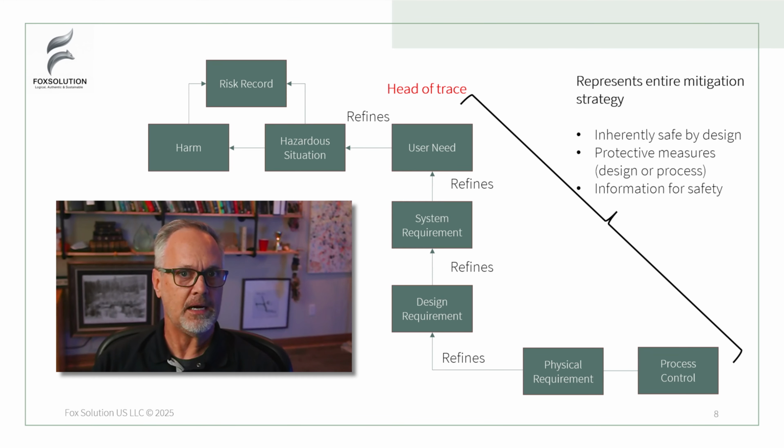Now, in many companies I've been involved in, and I would say maybe even more often than not, people don't look at the P1 and the P2 factor. They only look at P. And that's because they can see in the field how many occurrences of the harms have happened. But this mechanism, how does the hazardous situation play into it? And what is that occurrence rate of the hazardous situation? They don't understand that very well, so they just don't track it.